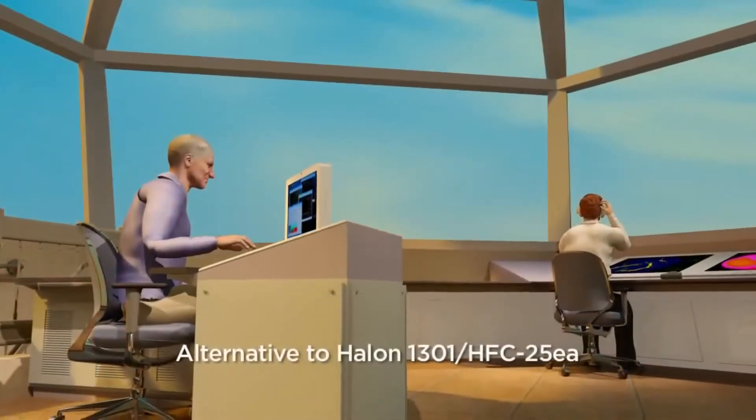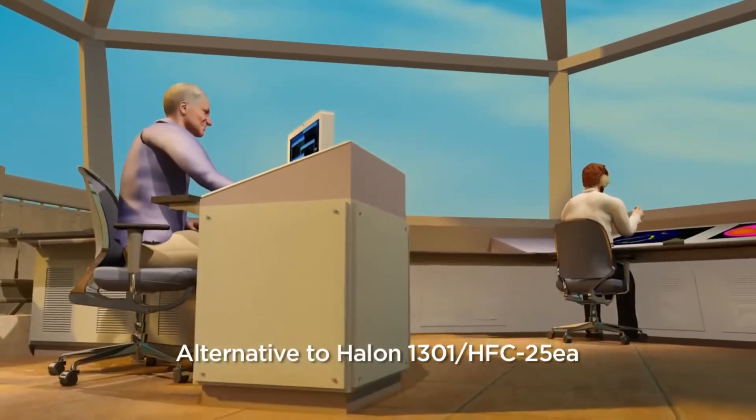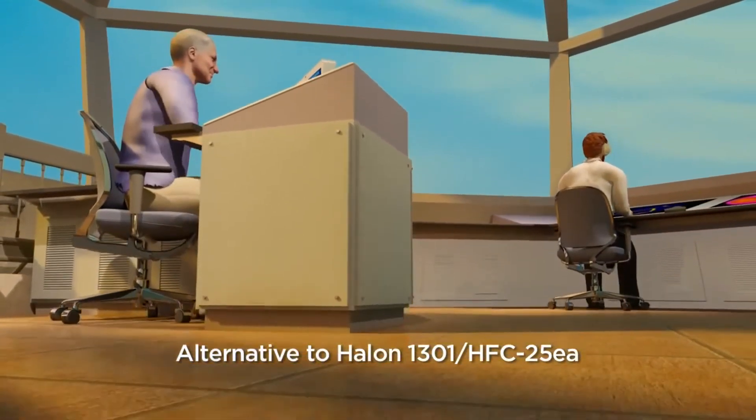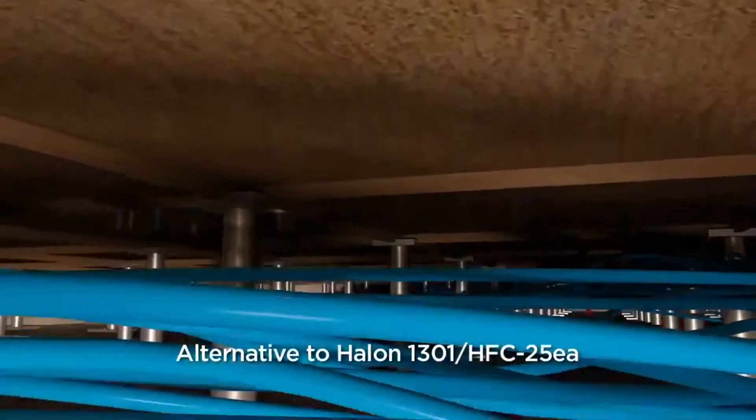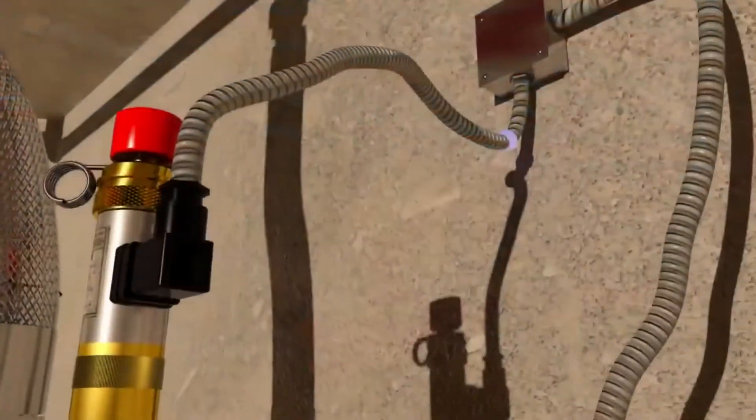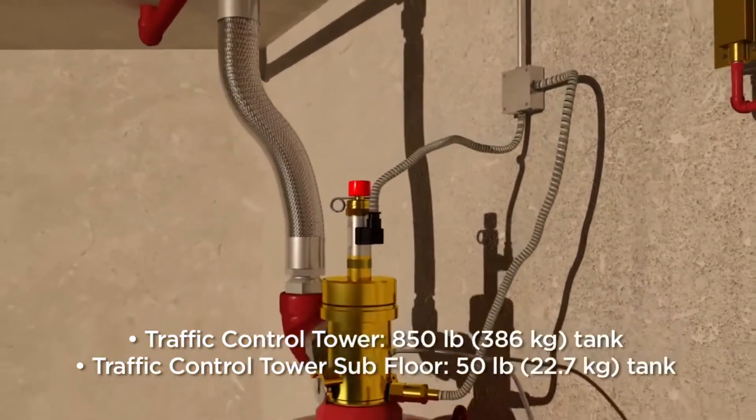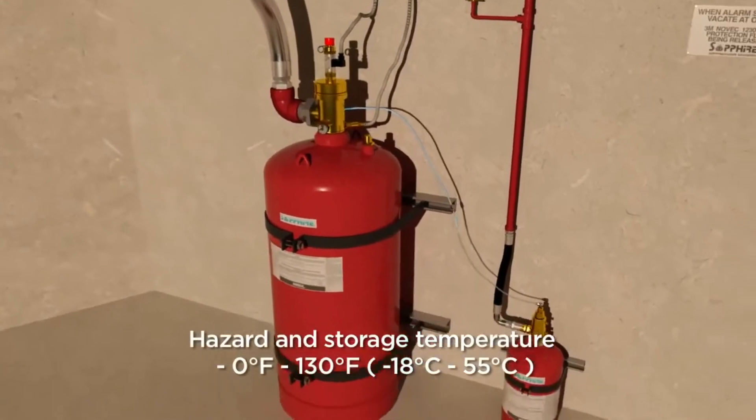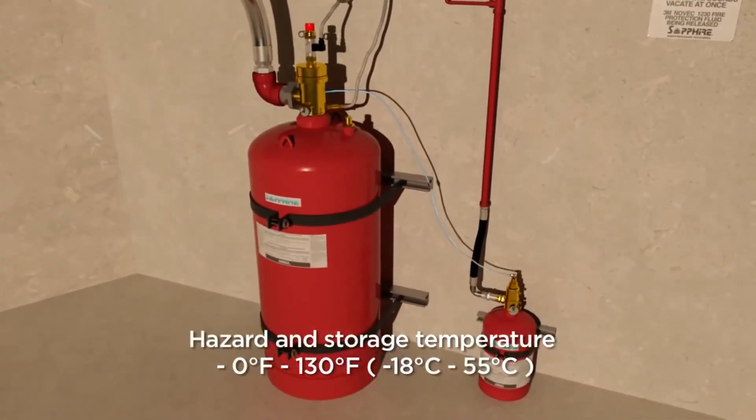The versatile Sapphire system can support the protection of multiple hazard zones, such as a main hazard area and subfloor. In multiple tank systems, the electric actuator opens the master valve. Additional tanks are actuated pneumatically through quarter inch stainless steel hose and a pneumatic actuator installed on top of each valve.